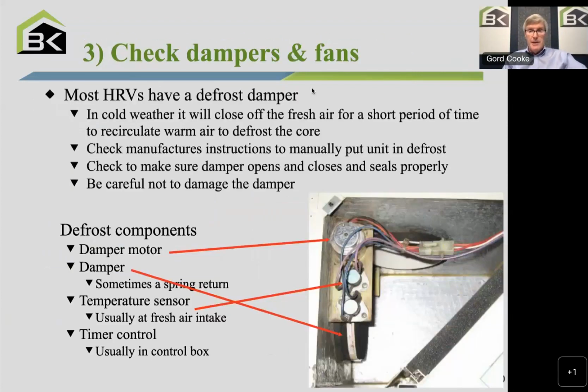And then most HRVs have a defrost damper. So let's go through quickly what that's about. Remember, I said cold air coming in, warm, moist air going out. Within the core, that warm, moist air gets colder and colder. And as it gets colder, condensate actually forms on the exhaust side of the HRV core. And in cold weather, below about -5 Celsius, that condensate will freeze. So whenever it's colder than -5, we need a defrost.